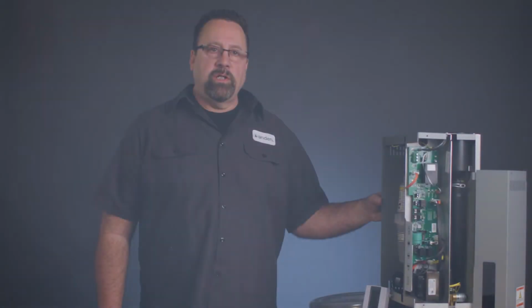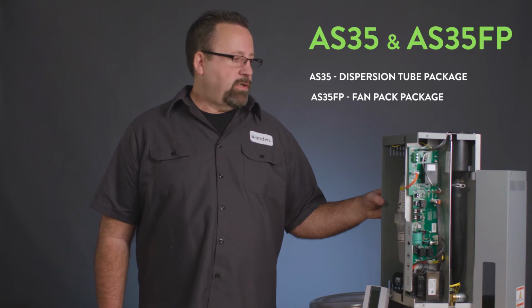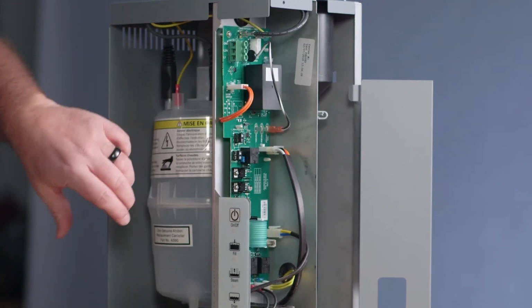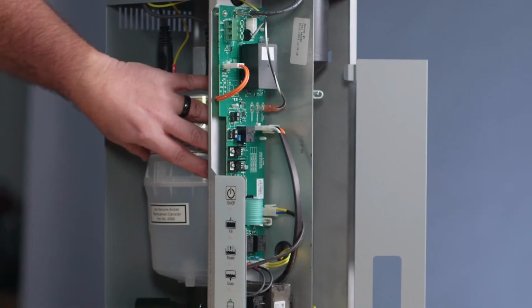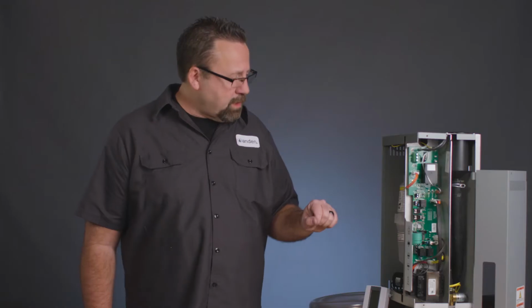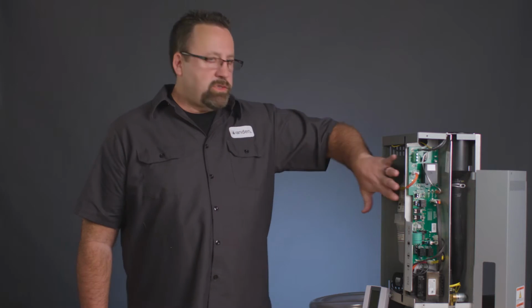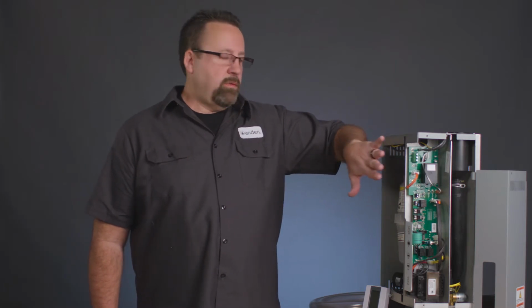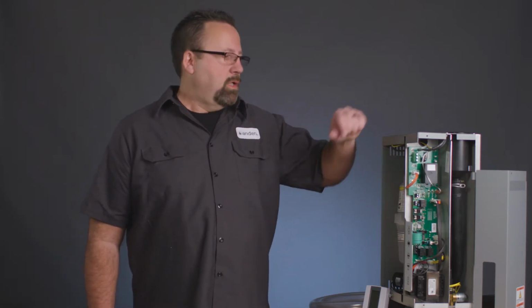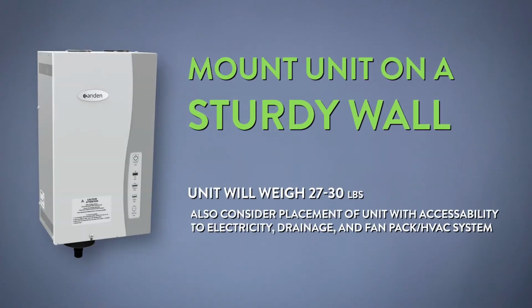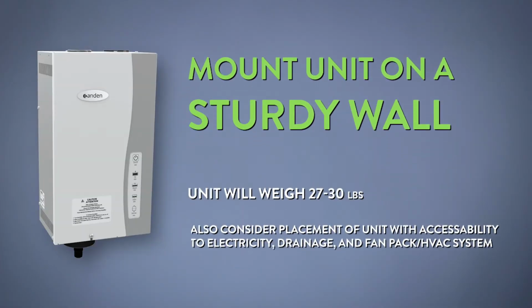All right, we're going to cover the installation of the AS35 steam humidifier, AS35 FP with fan pack. You can see I got the covers off of both sides of the unit here to expose the canister and the circuit board. A couple things to note. We're going to mount this right to the wall to make sure it's on a good, sturdy, studded wall. The unit's about 27 to 30 pounds when it's full of water and full of minerals. So you want to make sure that it's mounted onto a sturdy wall.